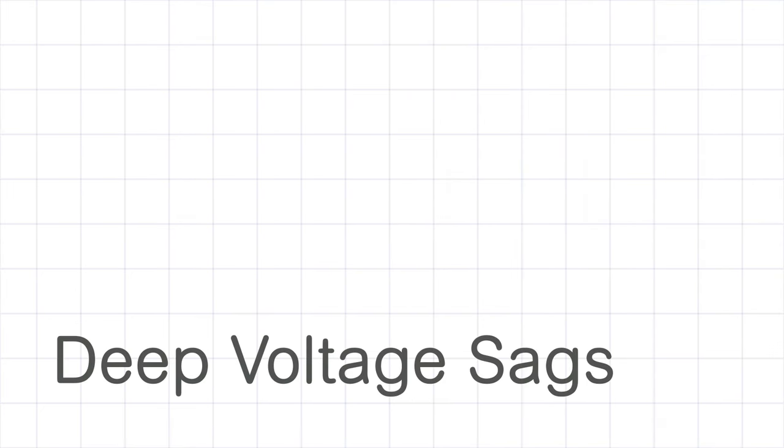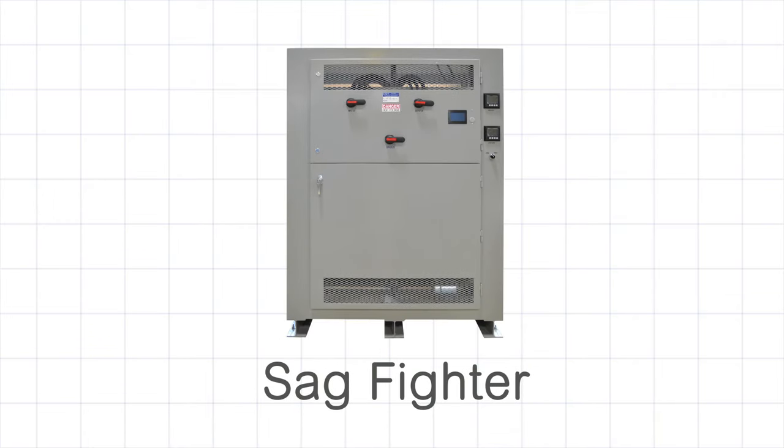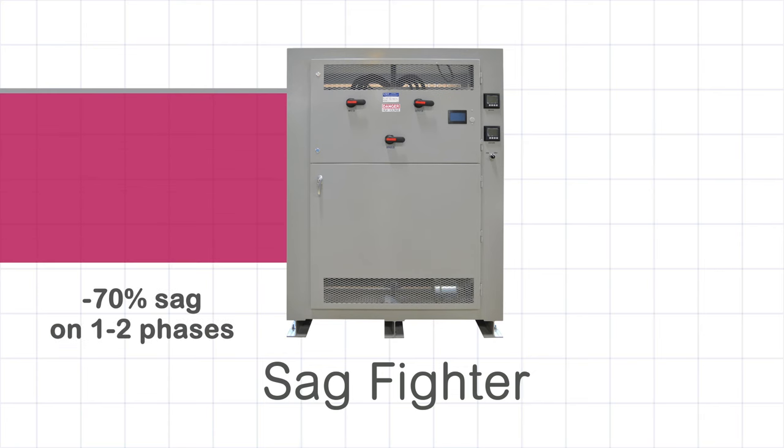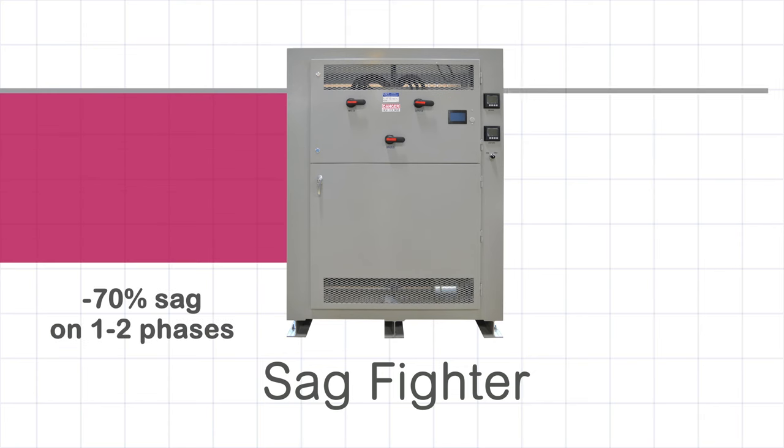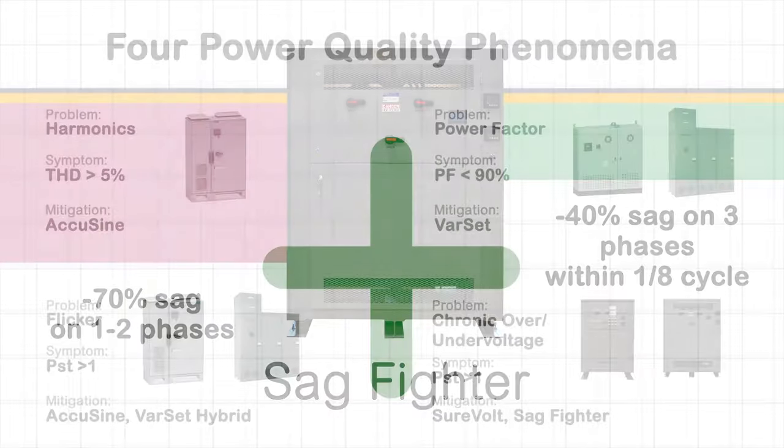Deeper voltage sag are normally caused by short circuit events and or by operation of a utility recloser. For these deep sag events, the sag fighter is the solution. It can correct for 70% sag on one or two phases or for 40% sag on three phases within one eighth cycle and boost the voltage back to 95% of nominal value.